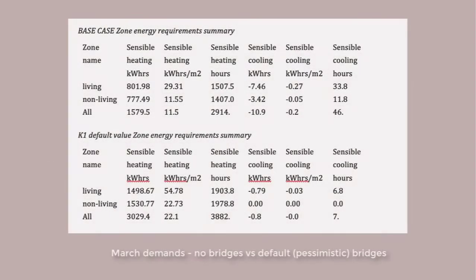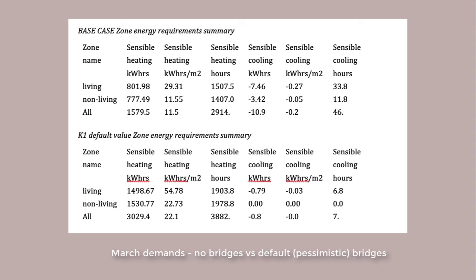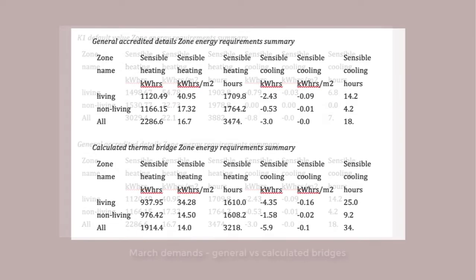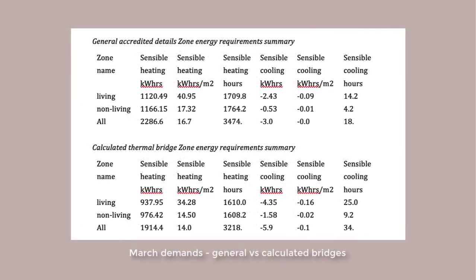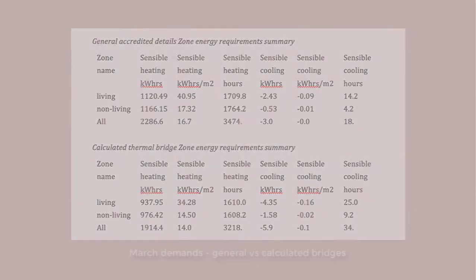If we assess the energy demands for the month of March for this typical base case of ignoring the thermal bridges, we get in the order of 1580 kilowatt hours. If we accept the default high values, we get in the order of 3000 kilowatt hours. Let's take the next step and compare default values with the use of generalized values for each of the junctions. The total heating demand reduces to roughly 2290 kilowatt hours. And if we are specific and improve the junction details, we might get down to roughly 1915 kilowatt hours, which compares back to the we-couldn't-be-bothered case of 1580 kilowatt hours.